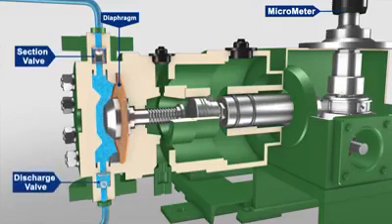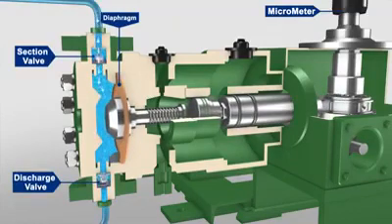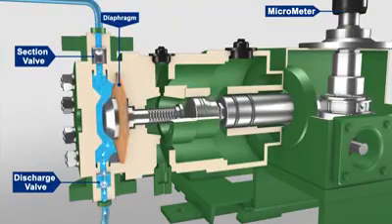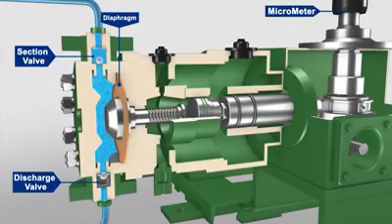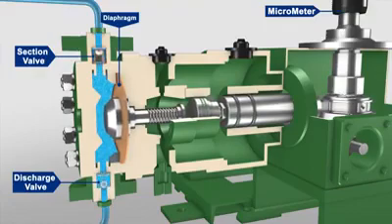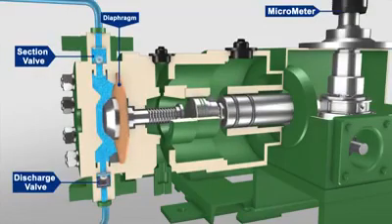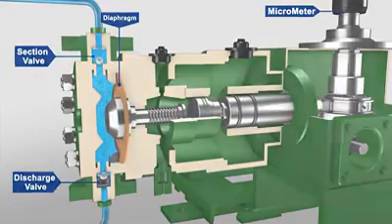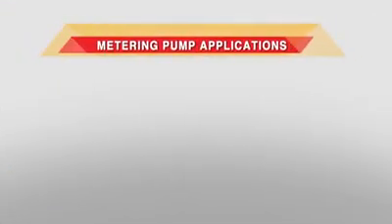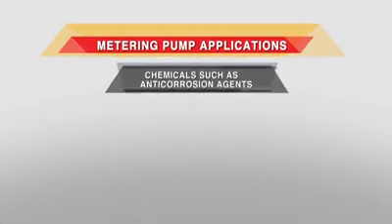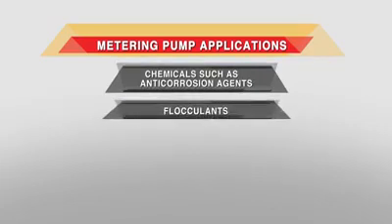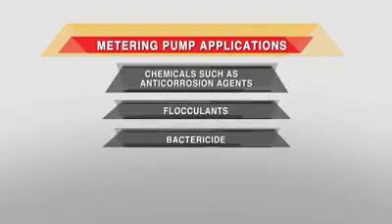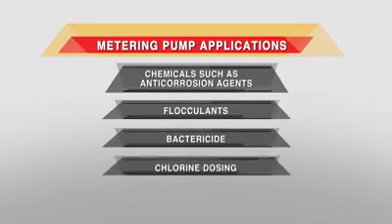A dosing pump will deliver this precise flow rate of chemical or other product by drawing a measured amount into a chamber and then injecting this volume of chemical into the pipe or tank being dosed. Metering pump applications include chemicals such as anti-corrosion agents, flocculants, bactericide, and chlorine dosing.